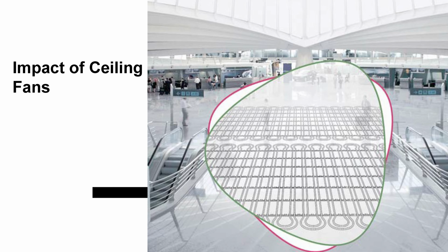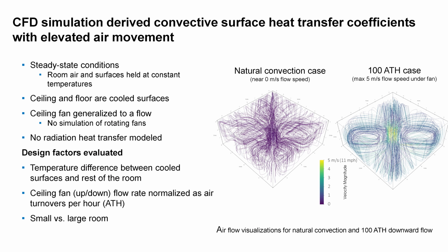So air movement is also a significant factor that affects the heat transfer in radiant systems. Normally in radiant systems, as we mentioned earlier, at least 50% of that heat transfer is radiation, and the rest is natural convection. But if we start increasing the air movement in the space, then we can increase the heat transfer on the convection side. To understand the magnitude of this effect, we developed a 2-phase simulation study where we first derive convective heat transfer coefficients for the radiant system using CFD analysis. Then we use these coefficients in EnergyPlus to understand the effects of various radiant system design factors.